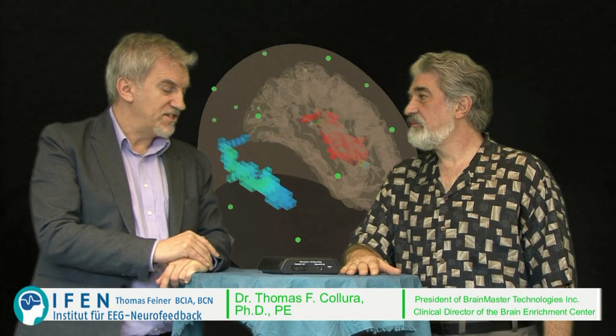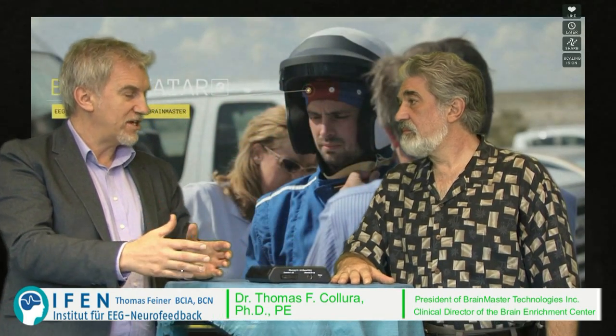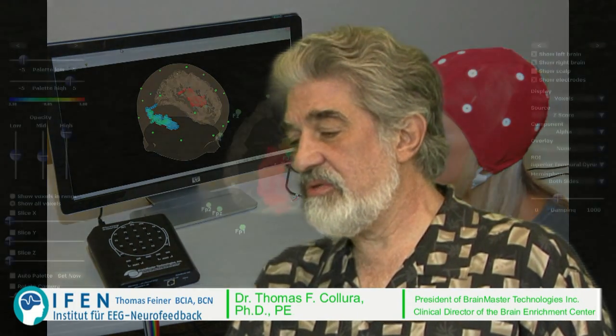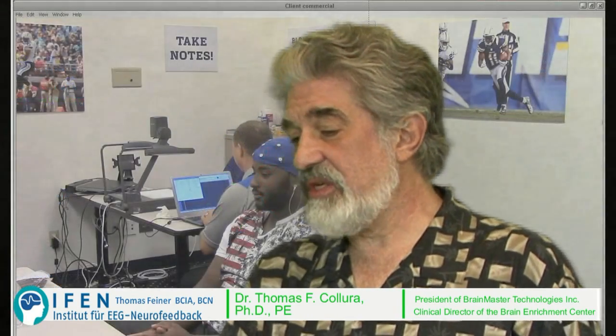This is also necessary for doing QEEGs or providing data during neurofeedback, like the Z-scores. When we do the signal processing, we use a combination of techniques, and our live processing technique is a mathematical transformation based on digital filtering — it's extremely fast. We actually process each sample as soon as it comes in. The response time inside the software is less than 30 milliseconds, which means we're able to respond to a brain event faster than the brain itself can respond to it.